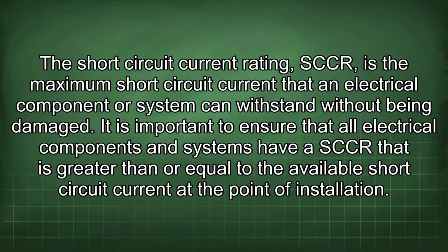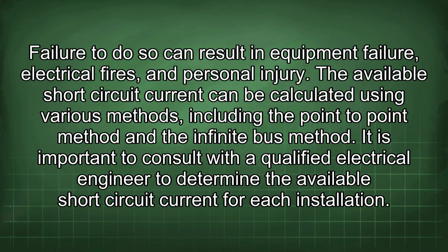The short circuit current rating, SCCR, is the maximum short circuit current that an electrical component or system can withstand without being damaged. It is important to ensure that all electrical components and systems have a SCCR that is greater than or equal to the available short circuit current at the point of installation. Failure to do so can result in equipment failure, electrical fires, and personal injury.